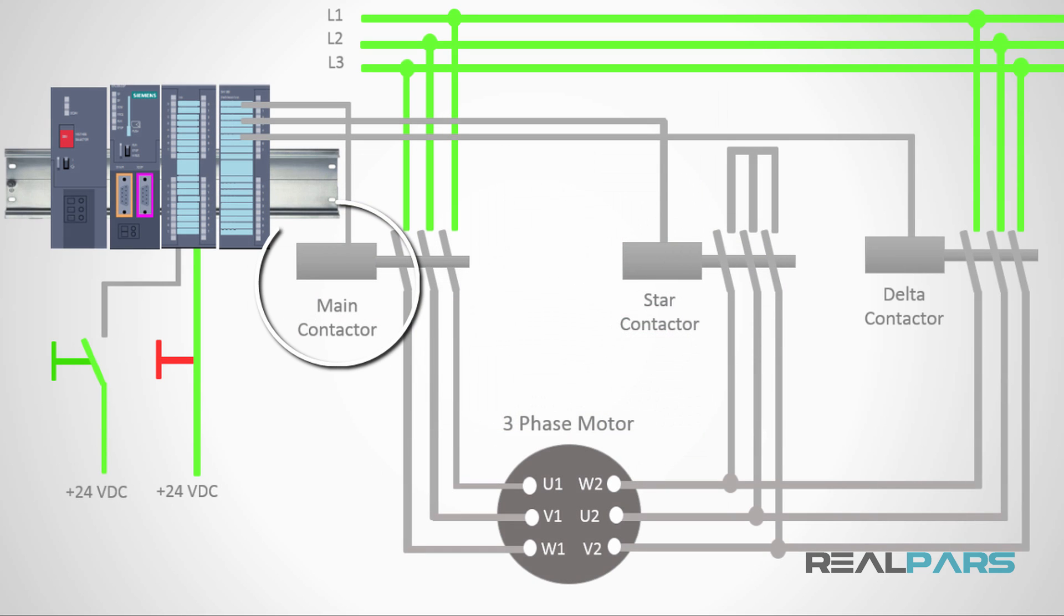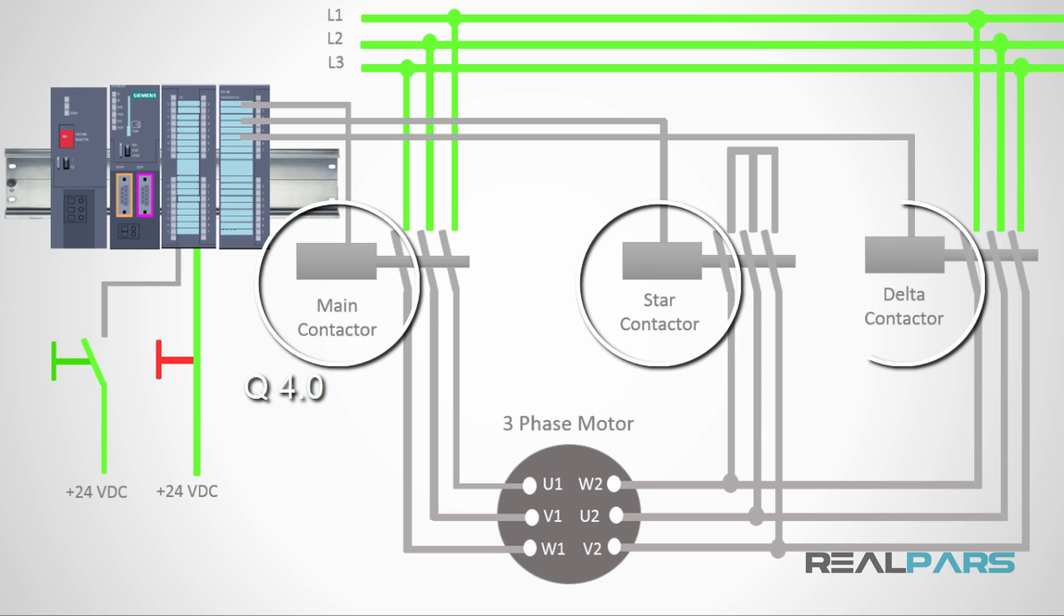If the main contactor is connected to the first output of the digital output module, the address that I can use for this output in the software is Q4.0. With the same assumption, the address for the star and the delta contactors that are connected to the second and third outputs are Q4.1 and Q4.2 respectively.